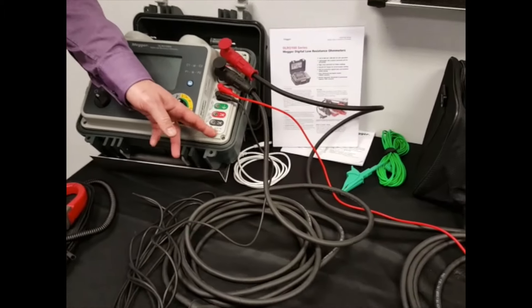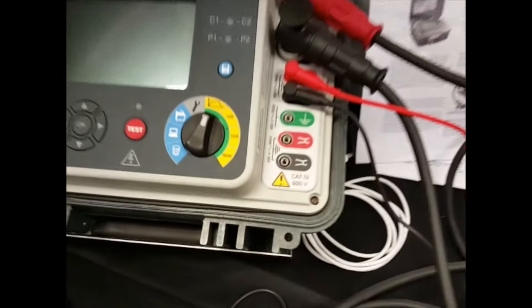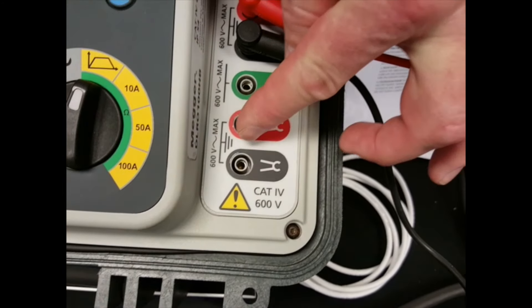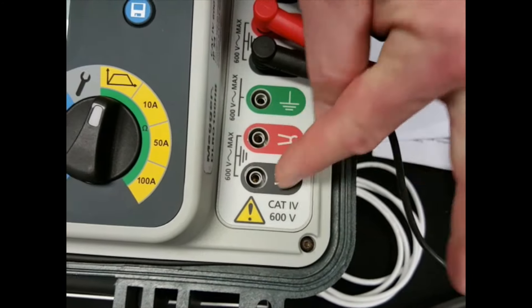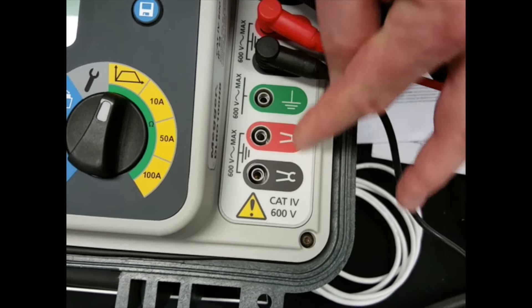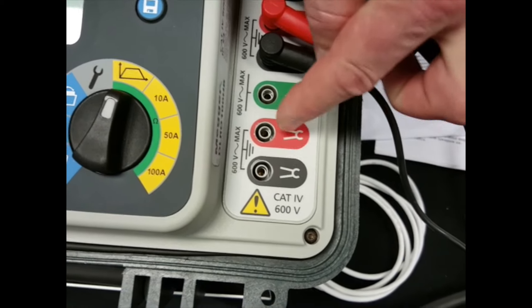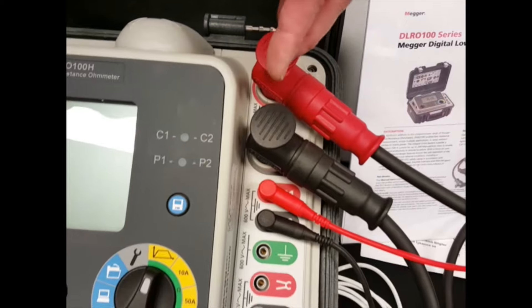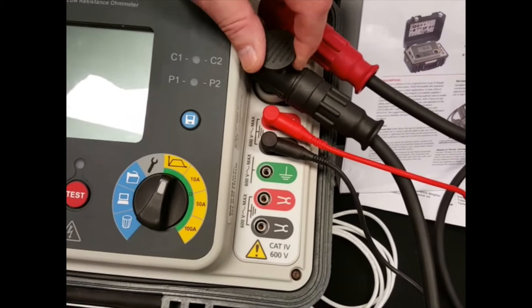This particular instrument, being Cat4 600V, is protected across all the terminals. You'll note here on the terminals these two terminals which are for the ground clamp terminals. These are 600V protected, so is the earth terminal. The potential and current terminals are all 600V protected to make sure the instrument remains safe.